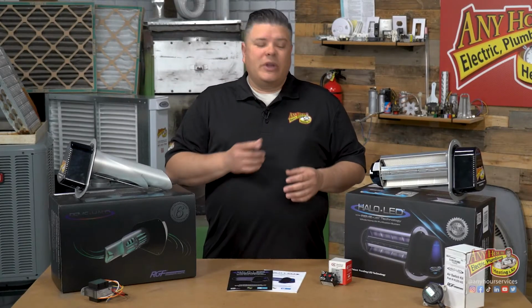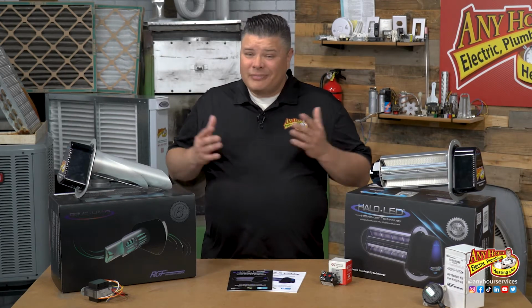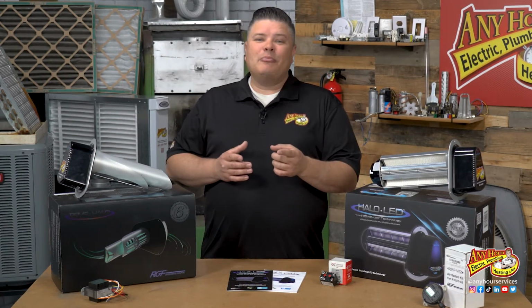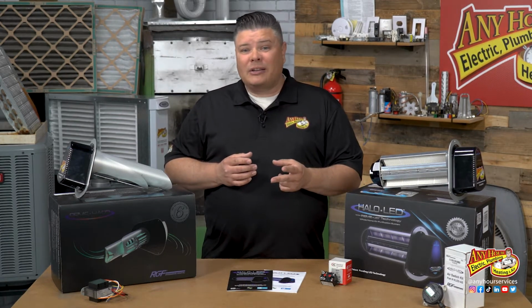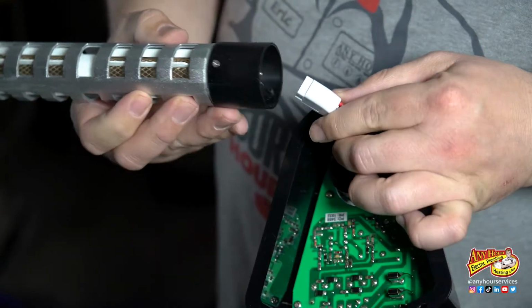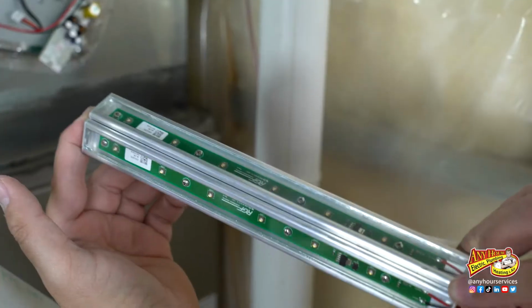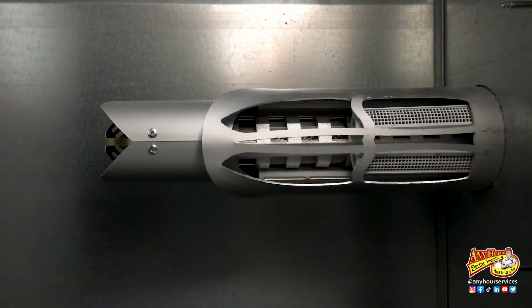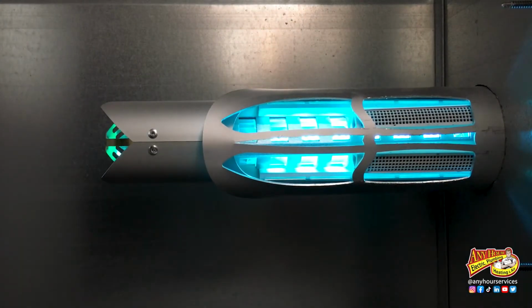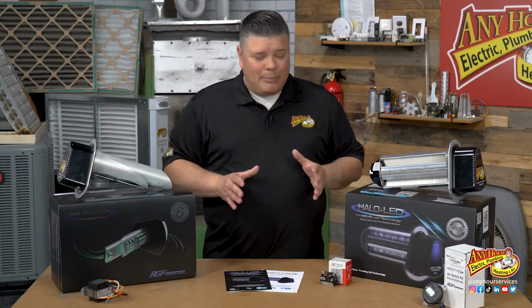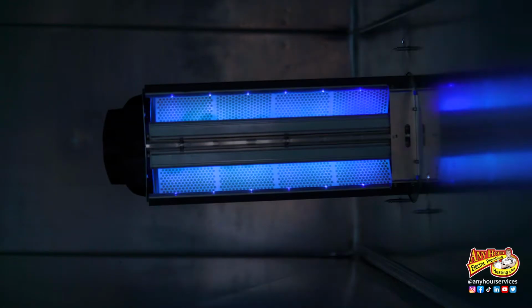The main difference between the Halo LED and the Reme Halo is its use of LEDs. So you're going to get improved energy efficiency and longer product life. Instead of changing the cell in the Reme Halo every 2 years, you get 5 years of protection with the Halo LED. The Reme Halo was designed to be on all the time in order to get the maximum life out of it, whereas the Halo LED is the exact opposite. It was designed to cycle on and off in order to get the maximum life out of it.